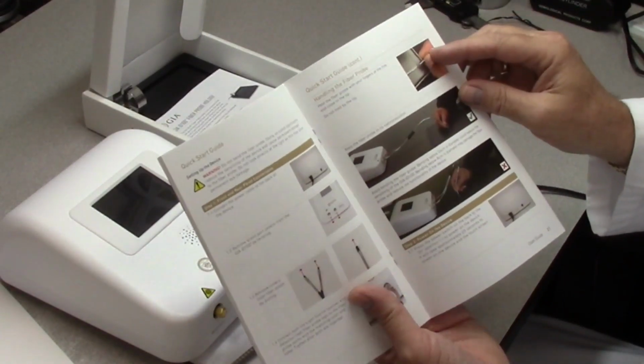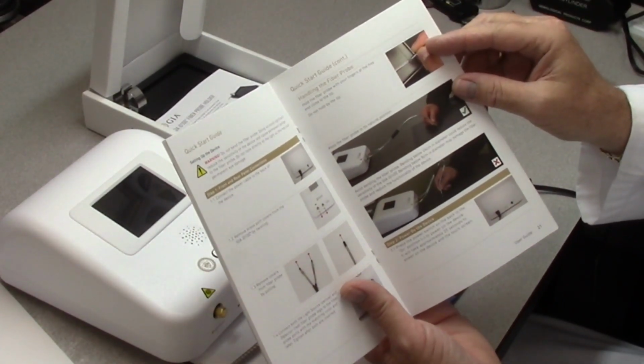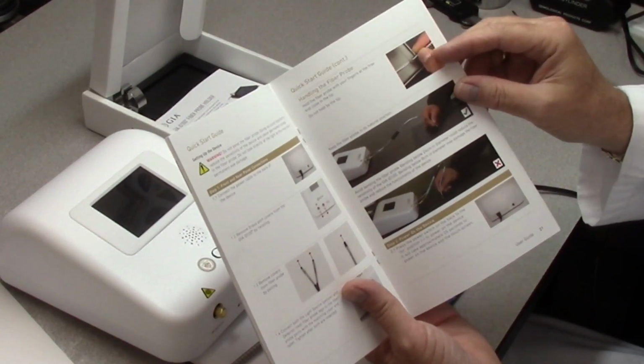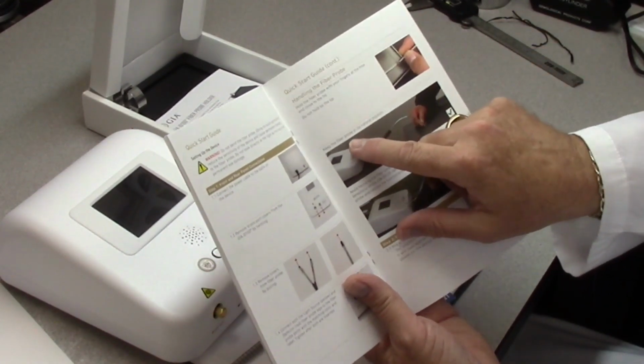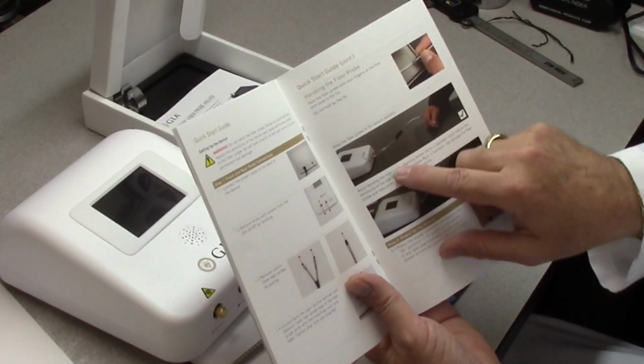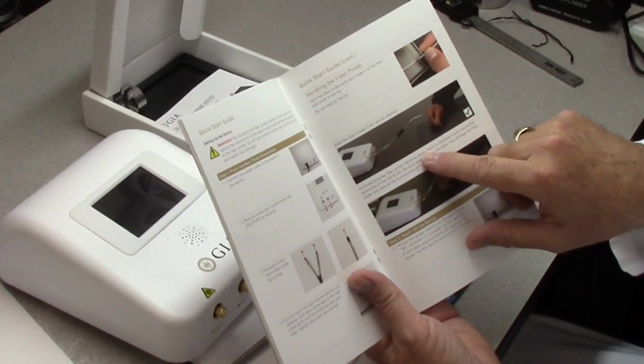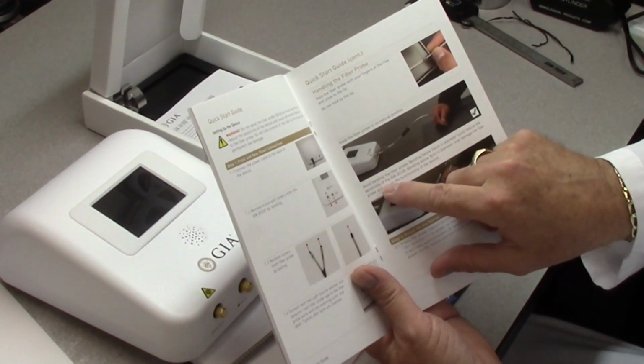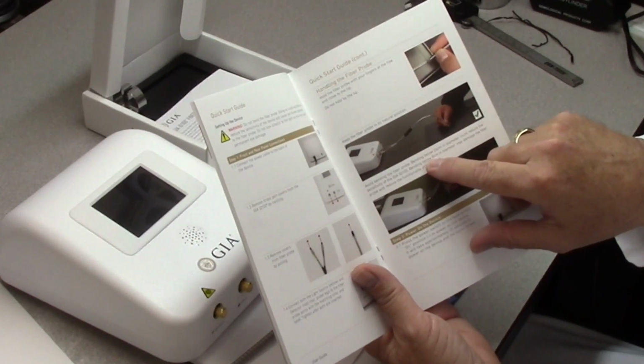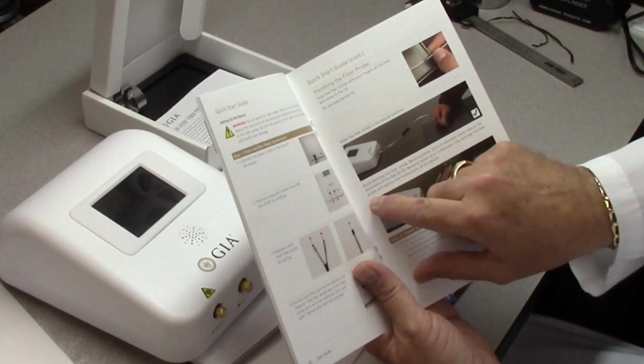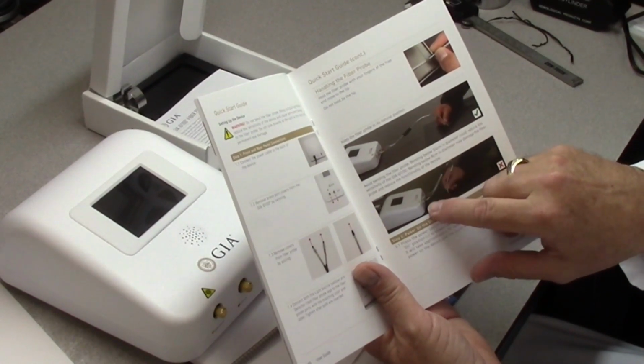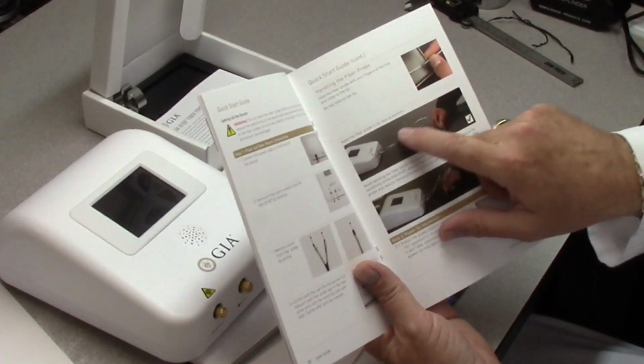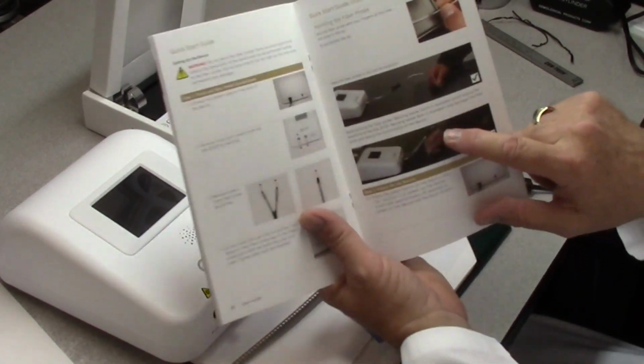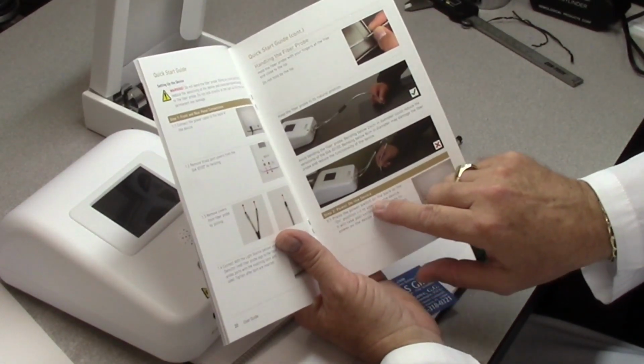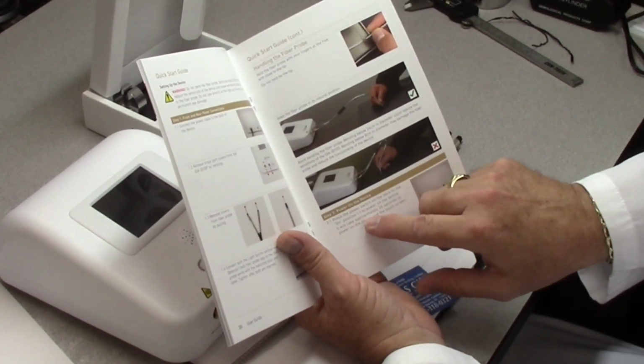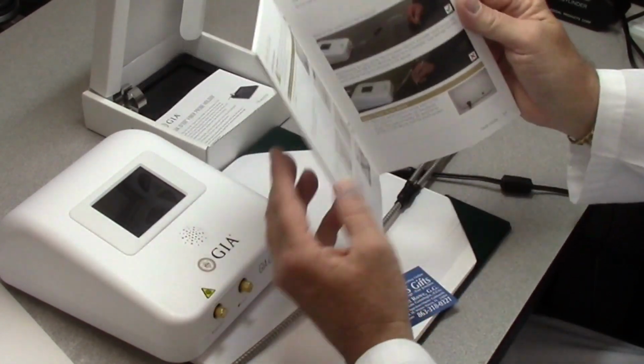It says handling of the fiber probe is to hold the fiber probe with your fingers at the free end close to the tip, and do not hold by the tip, and then keep the fiber probe in its natural position. Avoid bending the fiber probe. Bending below 24 centimeters in diameter could reduce the sensitivity of the GIA iD100. Bending below 8 centimeters in diameter may damage the fiber probe and reduce the functionality of the device. Do know that the replacement fiber probes are not cheap, so be sure not to do this. Press the power switch on the back to the on position to power the device, and it will take approximately 25 seconds to power the device on and touch the screen.